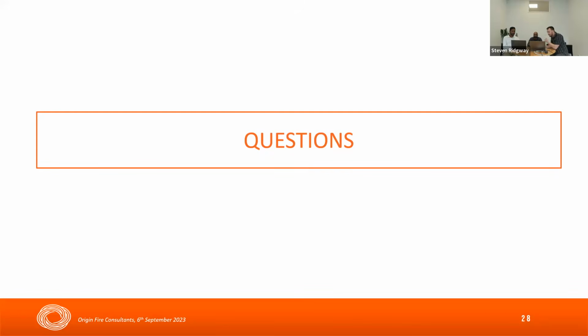Okay, thanks, Stephen. Next one for you, Vinny. How do we integrate the smoke spill fans and zone into the fire alarm system? I guess to control fans in a building, first you'll need an addressable panel, typically. Conventional panels can have relays within the panel, giving you clean contacts to operate ancillary services. But you'll have to confirm with the contractor installing the spill fans the type of contact they require, whether it's a normally open or normally closed contact. Typically, fire protection requires clean contact relays. So it's just a matter of coordinating where that third-party contractor requires an interface, how many relays they require, and the type of output they require, whether it's a normally closed circuit going open or vice versa.